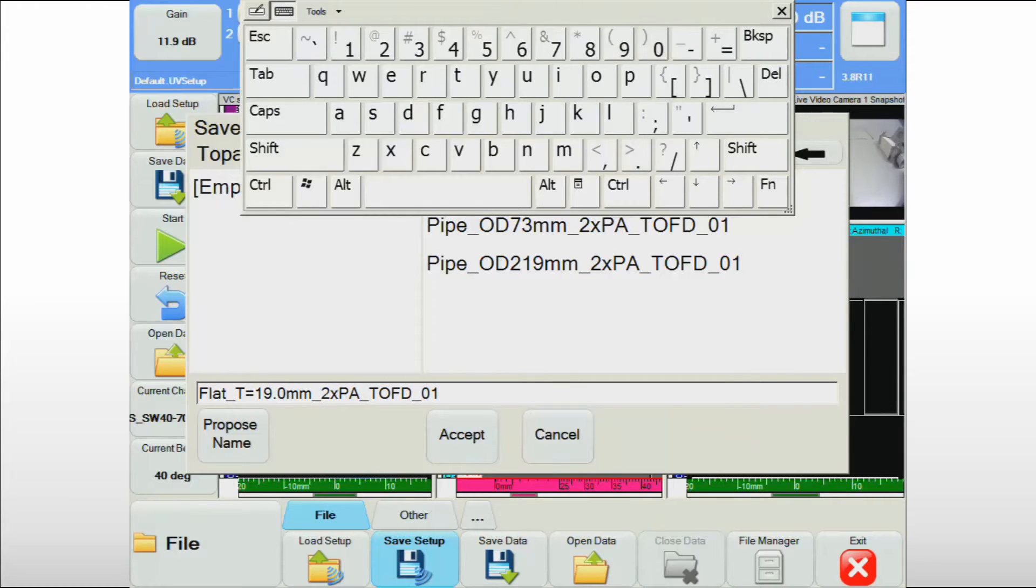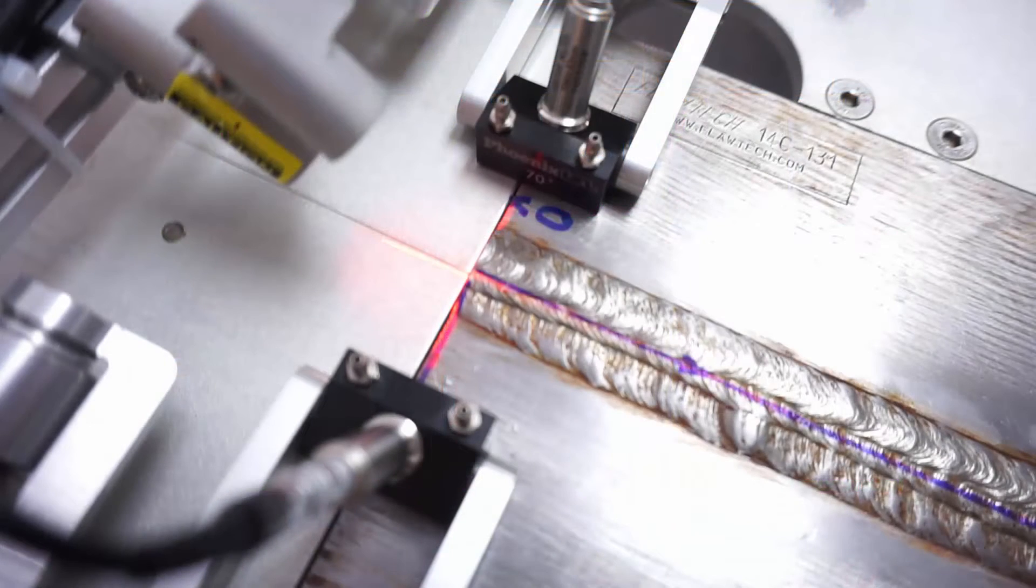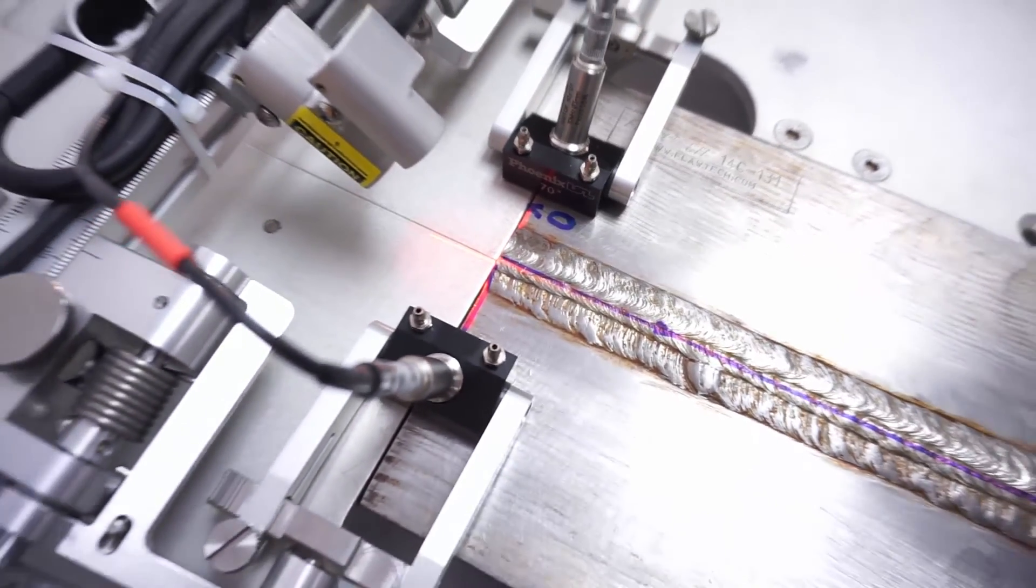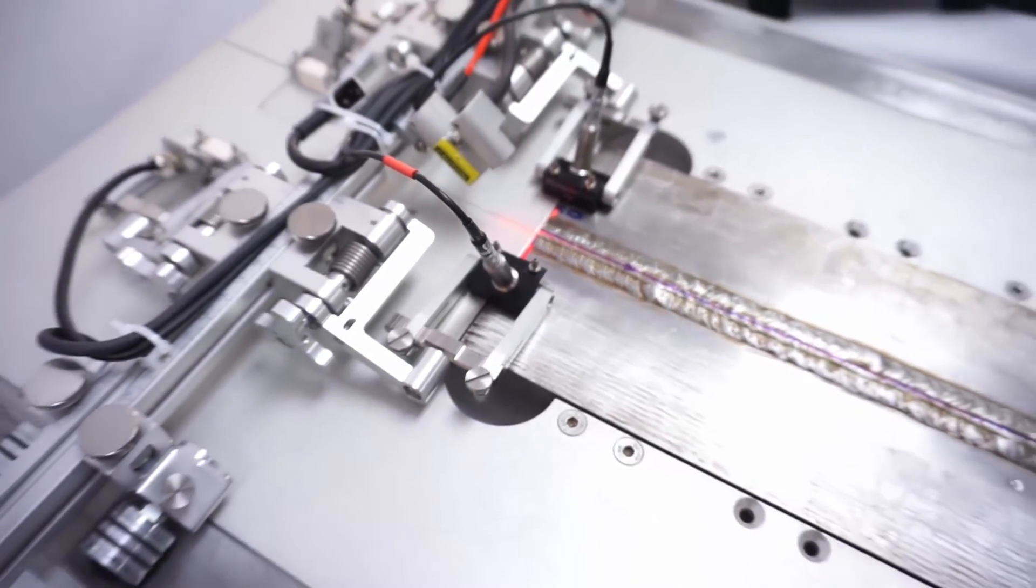During the job, the appropriate setup file can be simply selected from a list. In preparation of the inspection, the scanner is placed with the probes symmetrically on either side of the weld centerline. The laser guide can be very helpful in facilitating the installation.